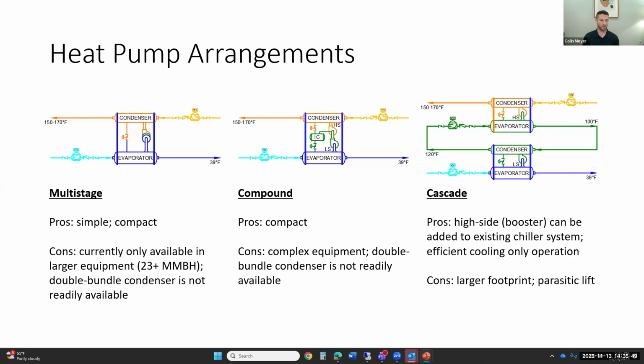So this is a very intriguing heat recovery unit, but the con is that it's currently only available on the market in larger sizes. 23 million BTUs per hour is kind of the smallest size. Also, in order to purpose the evaporator for beneficial cooling, if you don't need all the heating, you have to dump the hot water. You have to waste some hot water if you want to get beneficial cooling off of a machine like this. We've been pushing manufacturers to develop an option that has a lower temperature heat rejection condenser bundle or possibly a separate shell, but that's not readily available on the market.